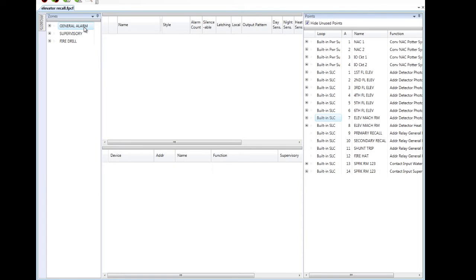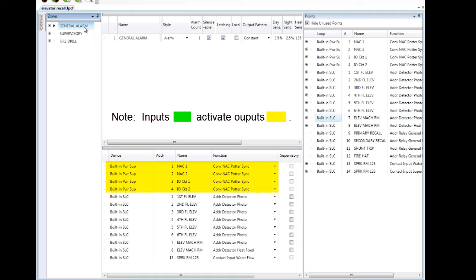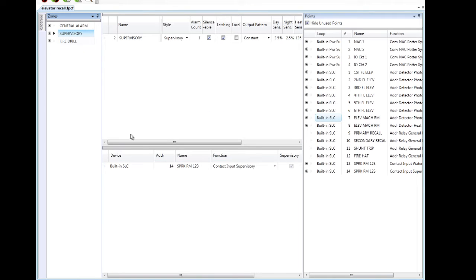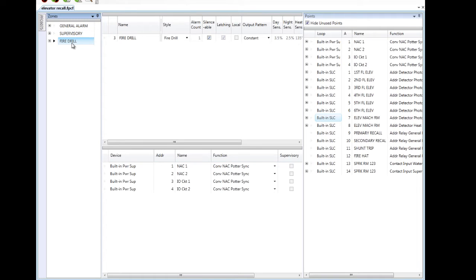I've already customized a few of my zones. My general alarm currently has all my notification circuits in it, as well as all of my smoke detectors, heat detector, and my water flow to activate those notification devices. I have a supervisory zone with my sprinkler supervisory point. And I've created a fire drill zone with my four notification circuits in it to trigger when the drill button on the front of the fire panel is pressed.